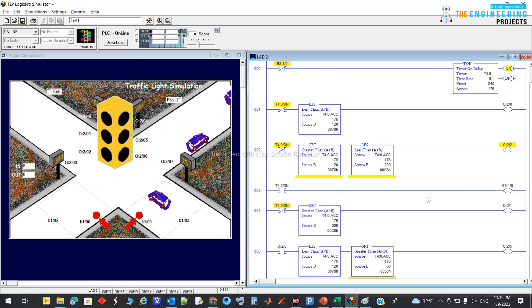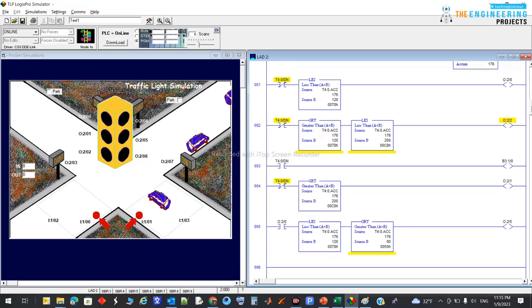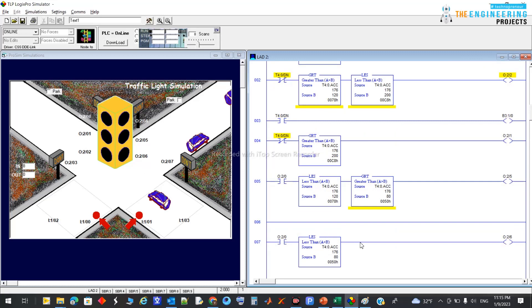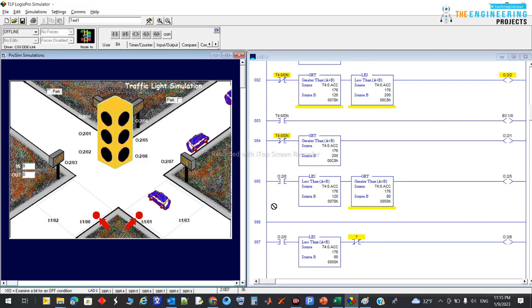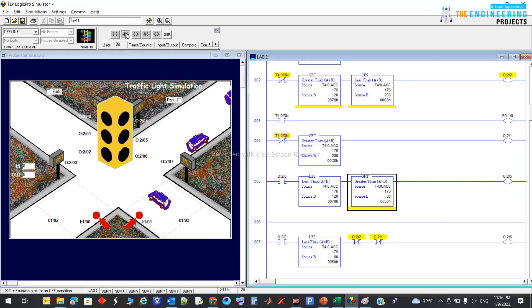I'll put a restriction: I will not open the green or amber on one side while the other side's green or amber is allowed. I know it's working fine now, but just in case — this is a matter of people's lives. So going to outputs Q2.6 and Q2.5: for Q2.6, which is the green for this side, I'll add a normally-closed contact to make sure the other side's green is not open simultaneously.